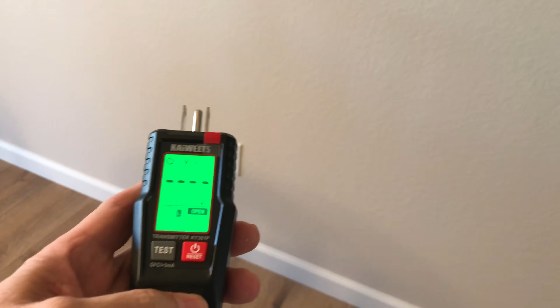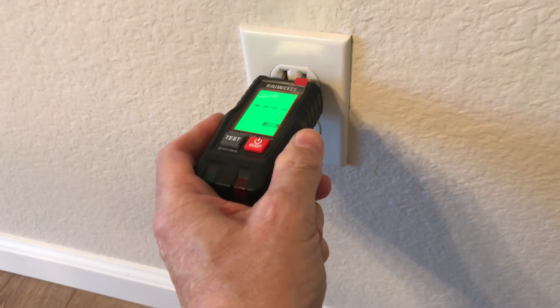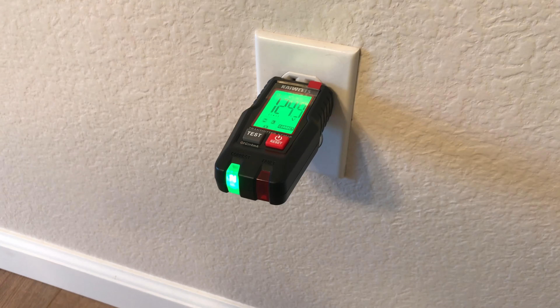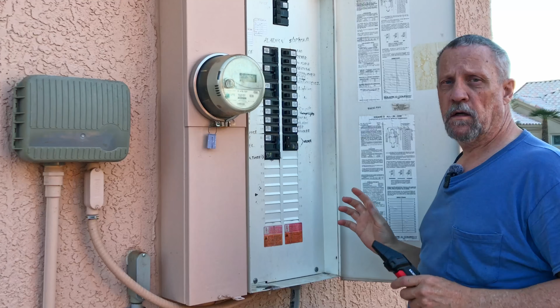Step one is simple. We turn on the transmitter unit and we plug it into the outlet that we're wanting to test. You see these lights? The green light indicates that the outlet has power and it is working. So it's important to note that these tools do not work if the outlet is not working, and you would need a tone tracer for that. But for today we have power, so the signal is being sent through the wires right now.